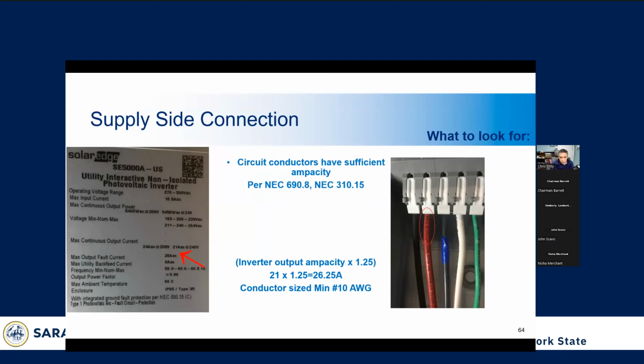All right, so moving on, with the supply side connection, you have to ensure that the conductors are sized appropriately. Again, you verify this by looking at the inverter nameplate for the max continuous inverter output current. Just like we did with the load side connection, multiply that by 125% for continuous load, and you verify that against the conductor size stamped on the wire itself. You can look that up online to determine what wire can hold what amperage. So that's how you do that.